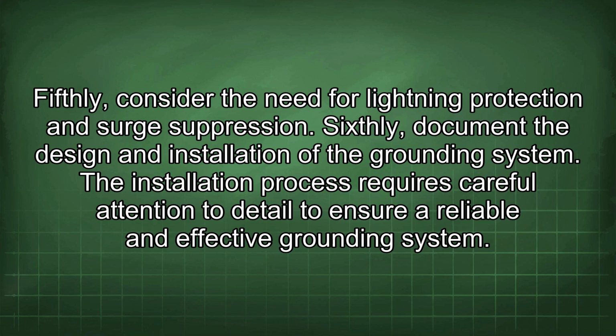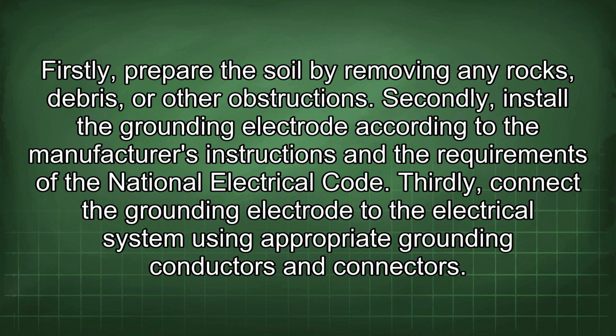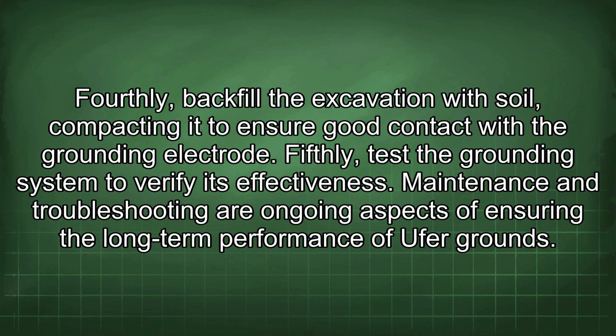The installation process requires careful attention to detail to ensure a reliable and effective grounding system. Firstly, prepare the soil by removing any rocks, debris, or other obstructions. Secondly, install the grounding electrode according to the manufacturer's instructions and the requirements of the National Electrical Code. Thirdly, connect the grounding electrode to the electrical system using appropriate grounding conductors and connectors. Fourthly, backfill the excavation with soil, compacting it to ensure good contact with the grounding electrode. Fifthly, test the grounding system to verify its effectiveness.